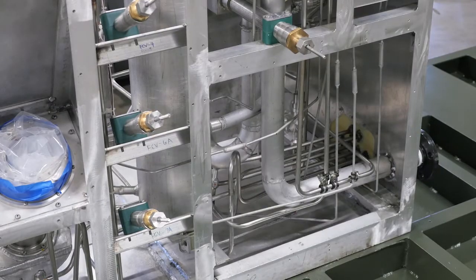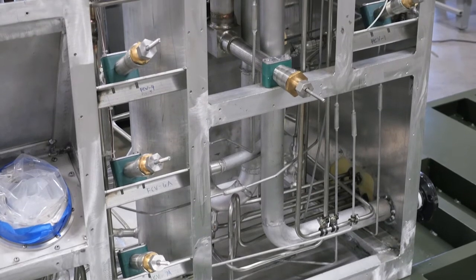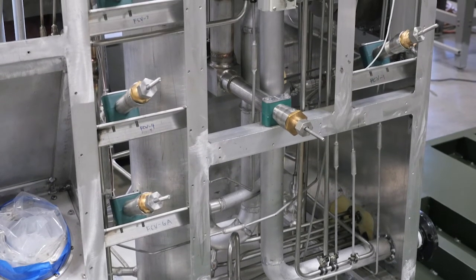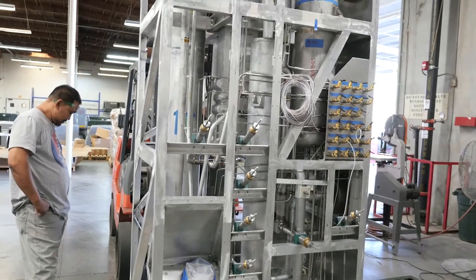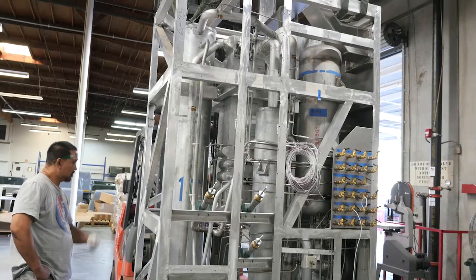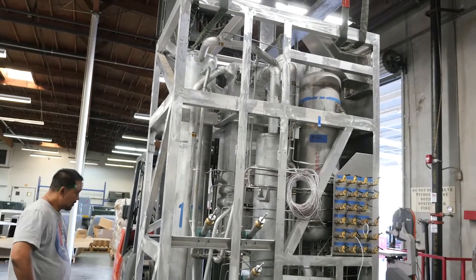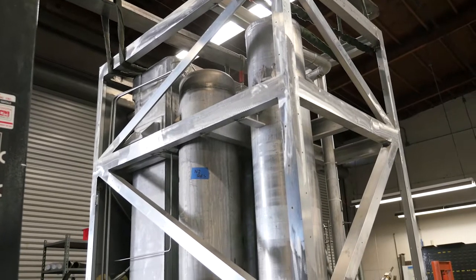This cold air then returns to the main heat exchanger, where it cools the incoming process air. The remaining portion of the process air, which did not enter the turbo expander, is further cooled to the point where crude oxygen begins to precipitate out.